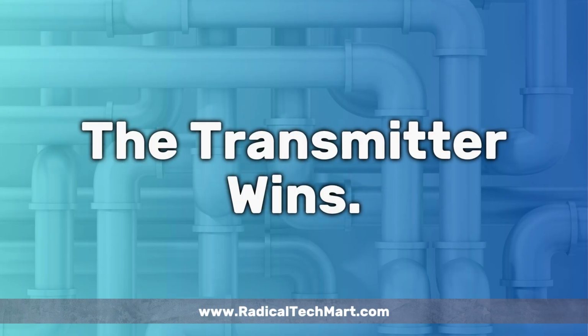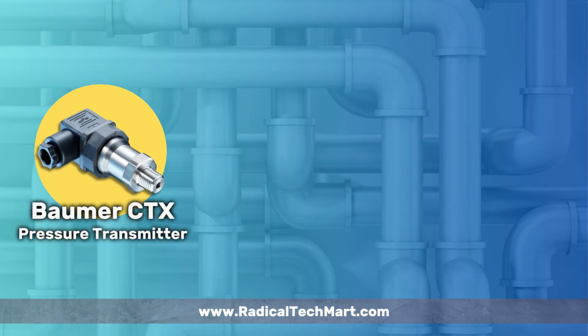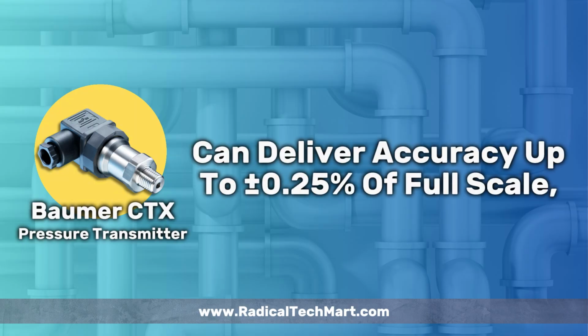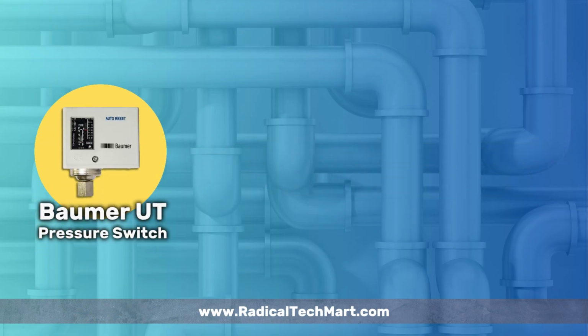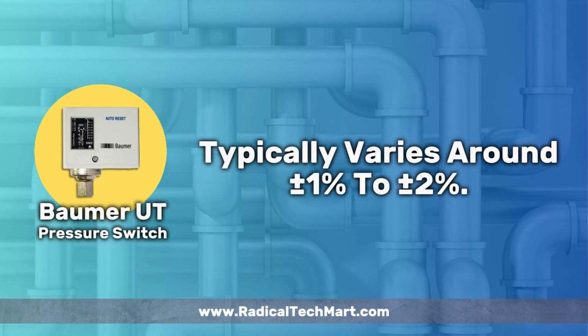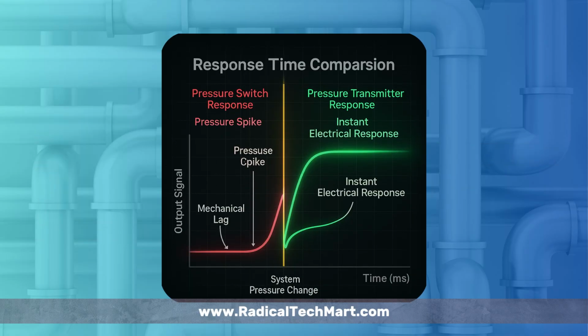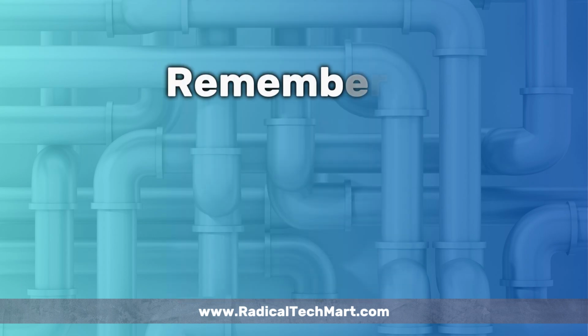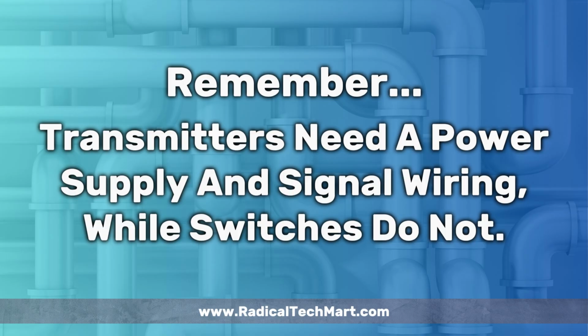analog signal. When it comes to accuracy, the transmitter wins. A Baumer CTX pressure transmitter can deliver accuracy up to plus or minus 0.25% of full scale, while a Baumer UT pressure switch typically varies around plus or minus 1% to plus or minus 2%. Transmitters also have faster response times, within milliseconds, whereas switches depend on spring movement, which is slightly slower. However, remember, transmitters need a power supply and signal wiring, while switches do not.